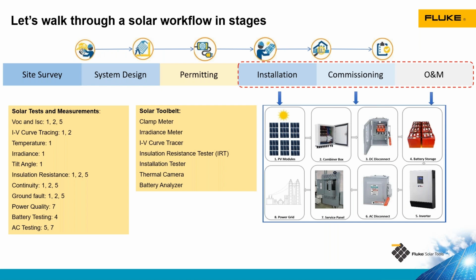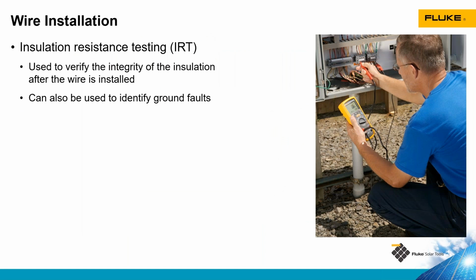There are many stages in the life cycle of a solar installation, from the design and development stage, but we're really going to focus on installation and especially commissioning and operations and maintenance, because that's where most of our tests are done. And Fluke, of course, is a test and measurement manufacturer, so that's mostly what we're focused on. During the installation phase, a really good test to perform is insulation resistance testing. This is making sure that the insulation of the conductor has not been compromised during the installation process.